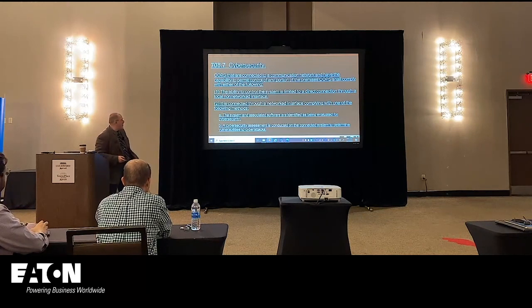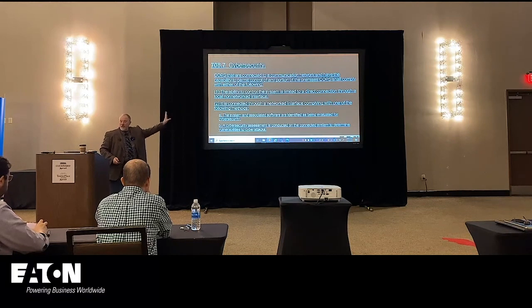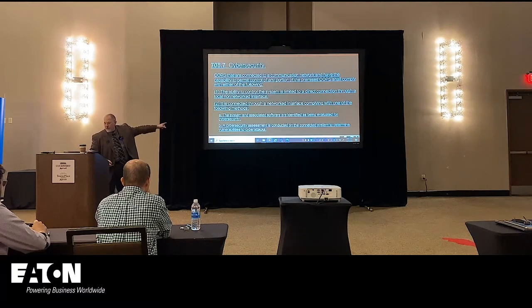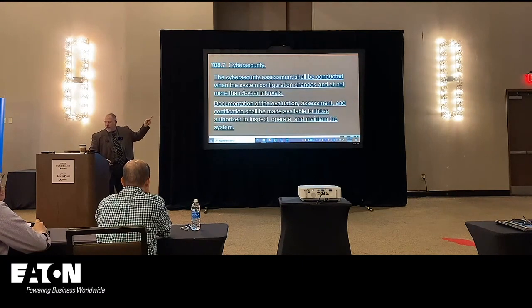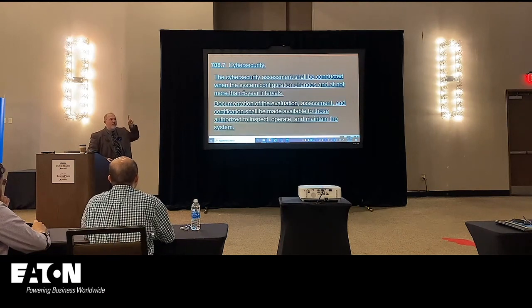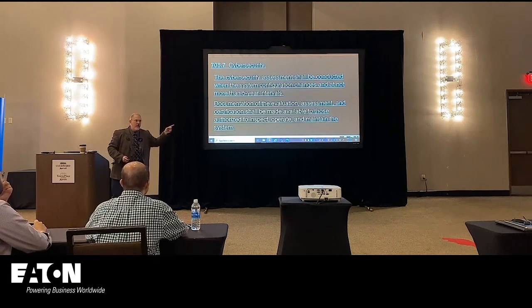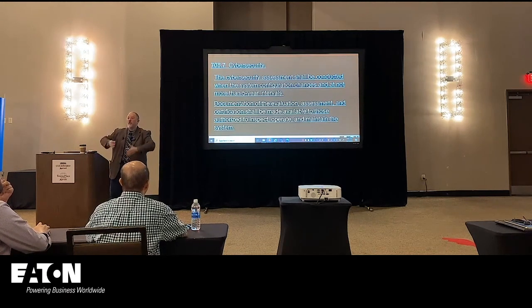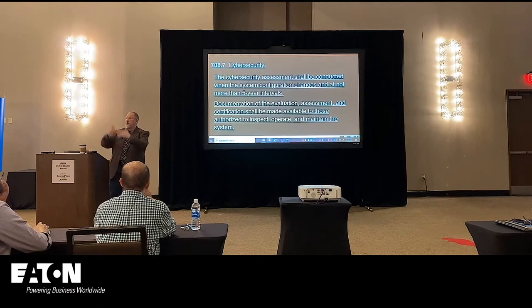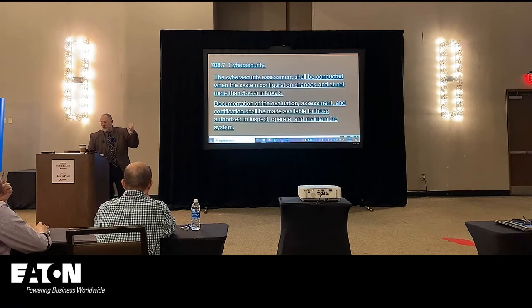There's your 708. Now here's the issue with this one. Okay, you'll see that, again, the two philosophies are here. Connected through a network interface, you have A, being evaluated for cybersecurity, B, doing the assessment. But the problem in 708 was this language right here, which is what failed it at the panel meeting. The National Electrical Code is an installation requirement. We don't look at it every 5 years. 70E tells us we need to do our systems analysis studies every 5 years because that's a part of your work plan, your safety plan. But the NEC, that doesn't necessarily belong in the NEC.